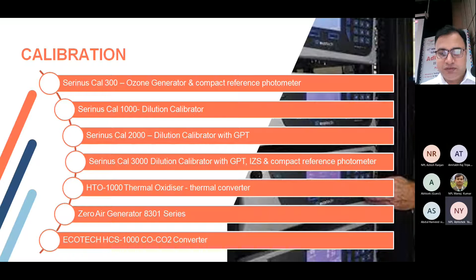From the calibration point of view, to calibrate these gas analyzers we have a number of options: the Serinus Cal 300 with ozone generator and compact reference photometer, then a dilution calibrator along with GPT, gas phase titration, which is basically required for NOx analyzer calibration as well as ozone analyzer calibration. Then we have the Serinus Cal 3000 with an internal ozone generator and reference photometer. So these are the number of options we have, along with the gas generator.